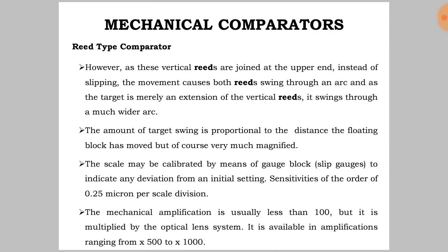However, as these vertical reeds are joined at the upper end, instead of slipping, the movement causes both reeds to swing through an arc. Since the target is merely an extension of the vertical reeds, it swings through a much wider arc. The amount of target swing is proportional to the distance the floating block has moved, but of course very much magnified. The scale may be calibrated by means of a gauge block to indicate any deviation from an initial setting.